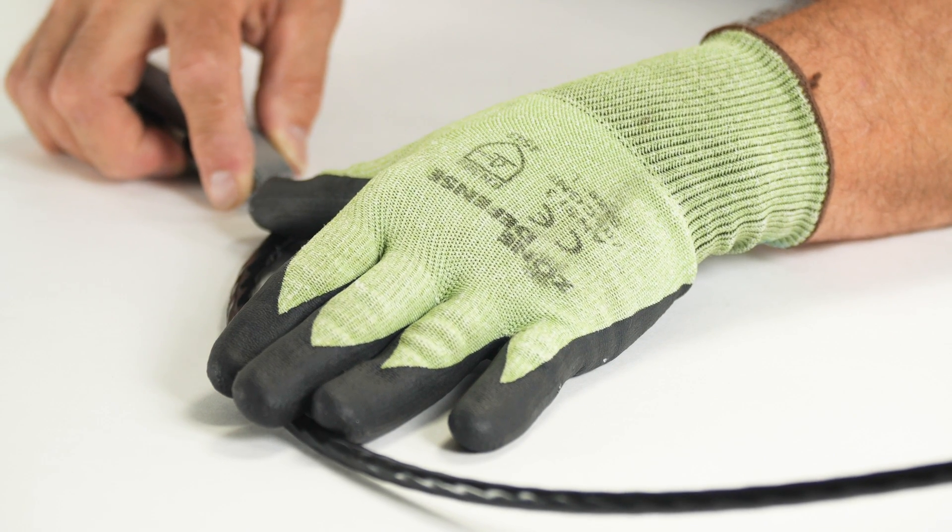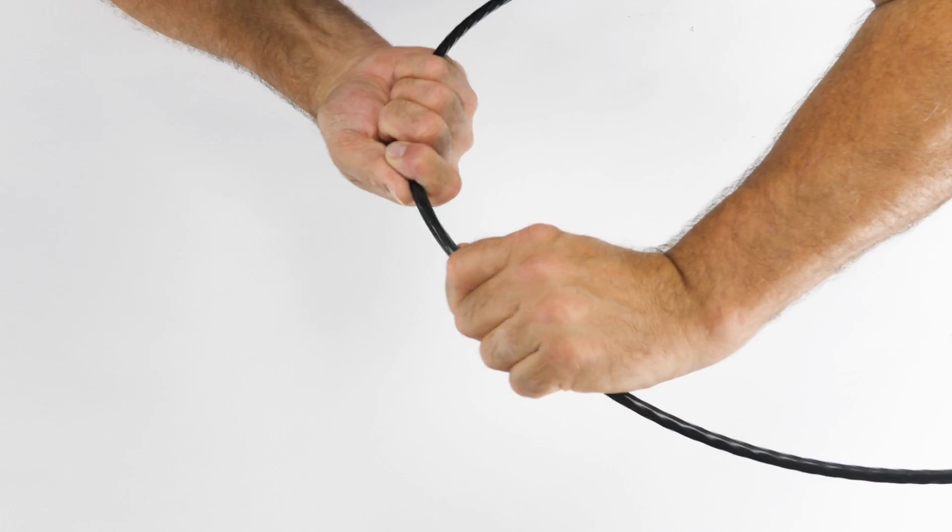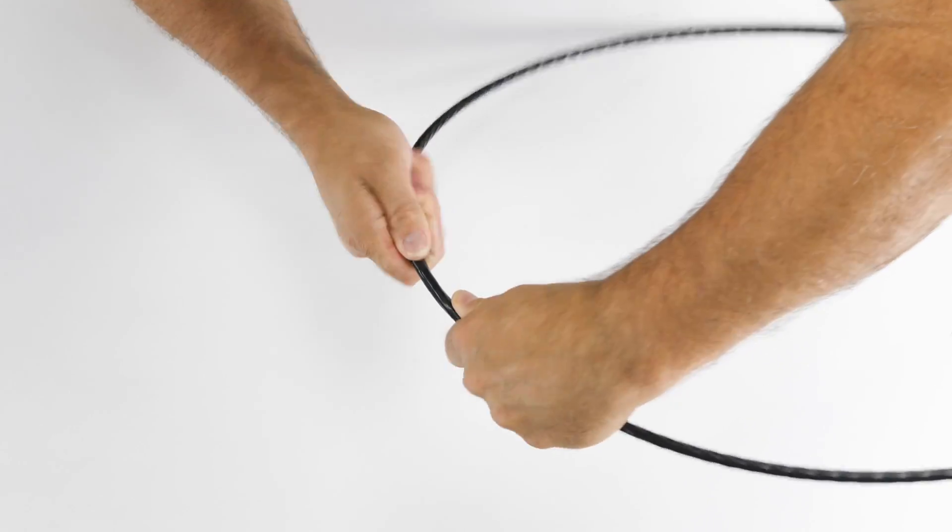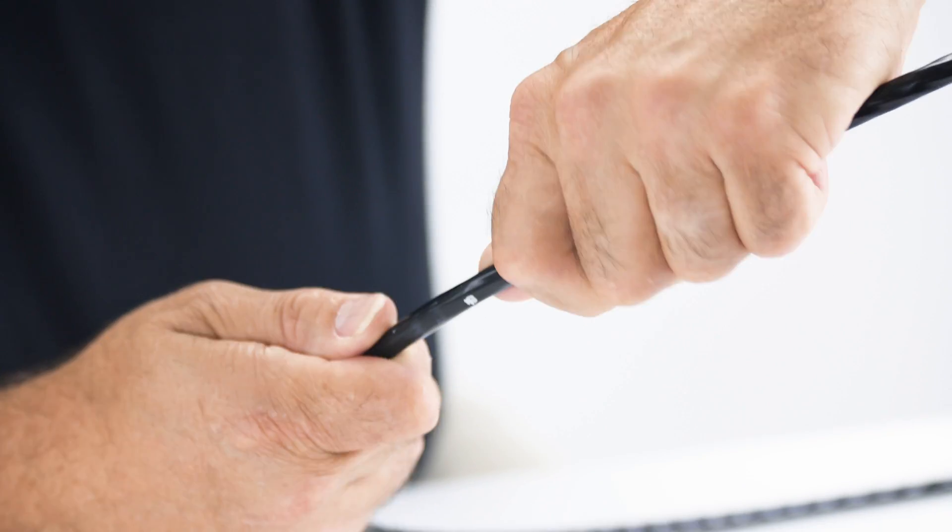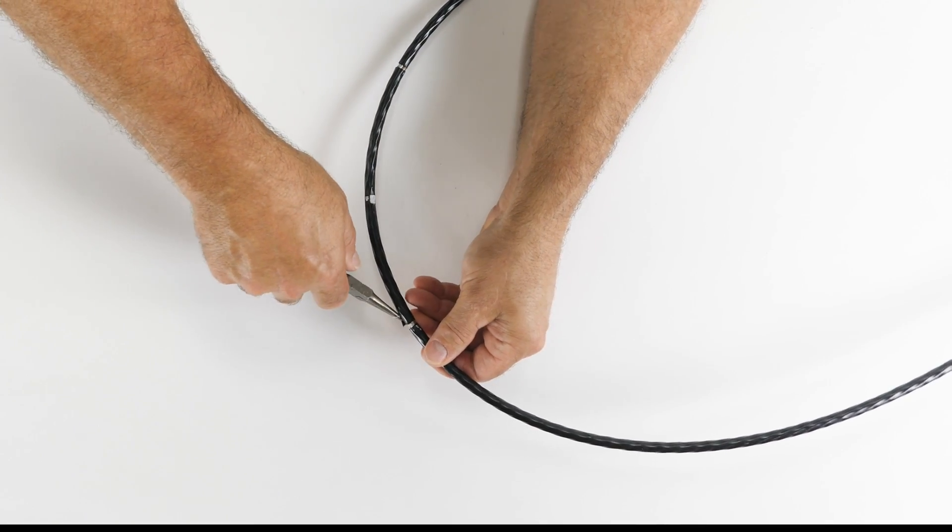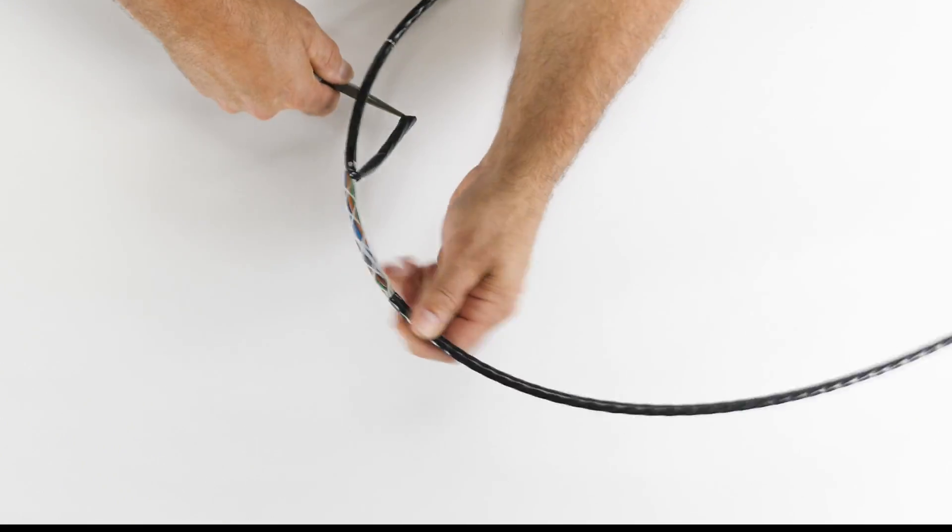After the surface has been scored, remove and store the cut-resistant glove. Place both hands within the 8-inch section of cable and slightly twist the outer jacket back and forth in order to open the jacket surface. At the ring-cut location, grip the jacket's edge with a pair of needle-nose pliers and remove the 8-inch portion from the remaining cable.